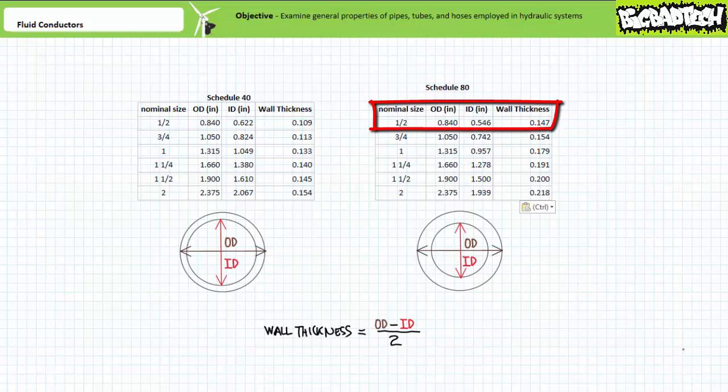You will note that the OD of the related nominal half inch pipes is the same and the ID is comparatively smaller for the higher schedule pipe. This correlates to a thicker wall, thus suitability for higher pressure applications.